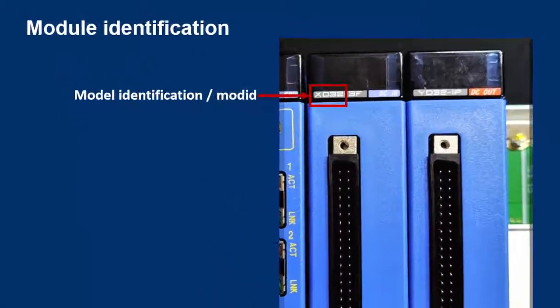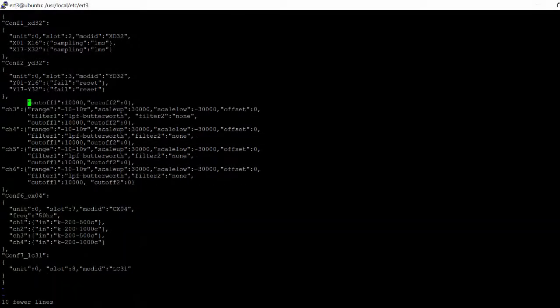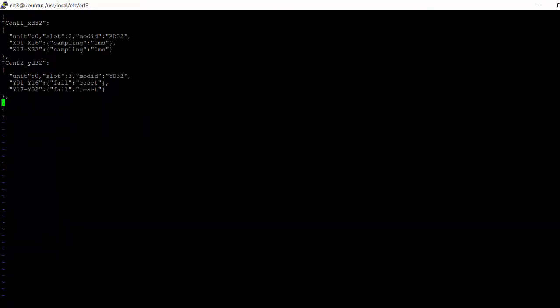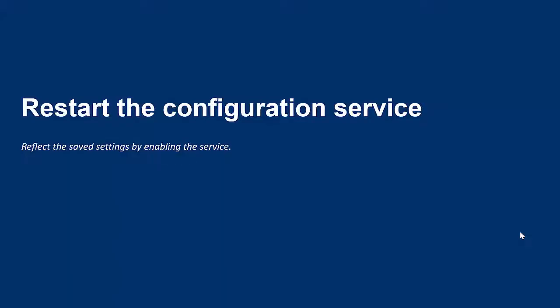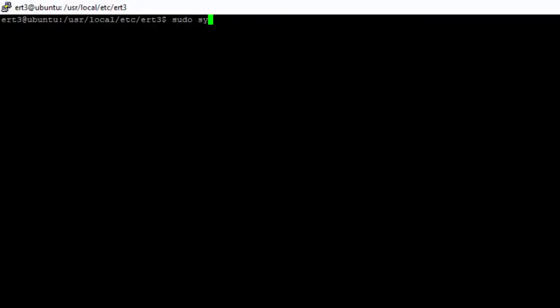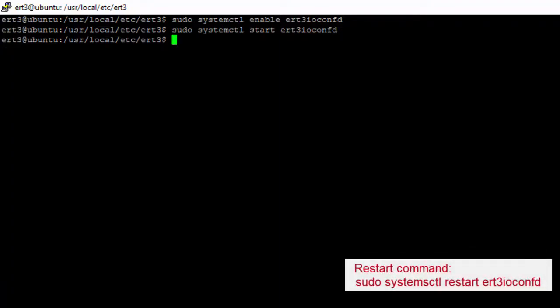Mod ID is the identification for the module type. The mod ID of each module can be found on the hardware unit. Since we have connected only the digital input and digital output modules, delete the remaining settings. Once the settings are configured, save the file and exit. To reflect the saved settings, enable the service by running the following command — these settings will be retained even after you reboot ERT3 Plus. Start the service and check the status; if the service is already running, use the restart command.